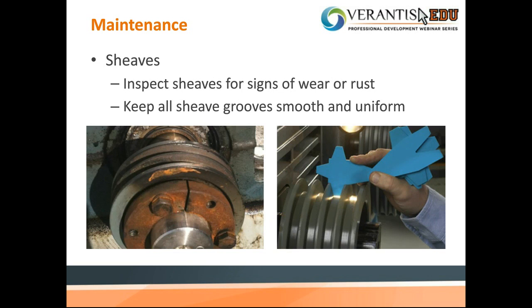So also during inspection, you want to inspect the sheaves. So basically inspect the sheaves for signs of wear or rust. That picture on the left is a well-used sheave that's been in service for some time, but you can see it's rusted out and is definitely in line for replacement. Whereas the picture on the right shows a basically brand new one where we're looking at the grooves to make sure it's properly in line. And groove gauges are available for your different sheaves. Any sheave supplier, you should be able to purchase them through there.